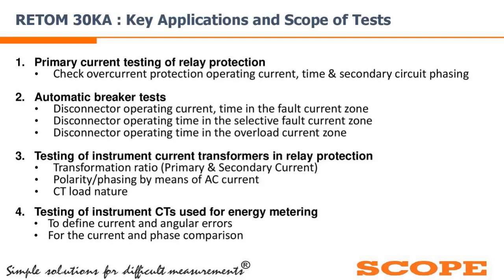For automatic breaker tests we can check: disconnector operating current and time in the fault current zone, disconnector operating time in the selective fault current zone, and disconnector operating time in the overload current zone. For testing of instrument transformers, we can easily check the primary-secondary current relationship, polarity of the CT, CT load nature, and testing of revenue metering CTs to define current and angular errors. We can also perform current and phase comparison.